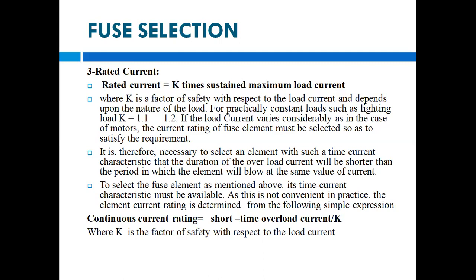To select the fuse element, its time-current characteristic must be available. So the continuous current rating is equal to the short time overload current divided by K.